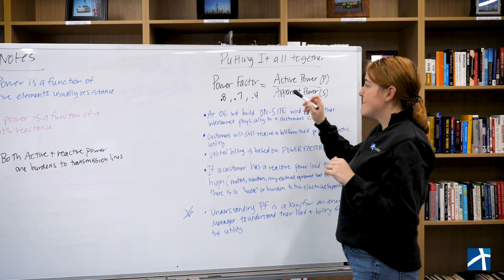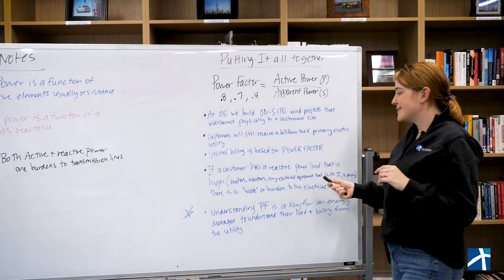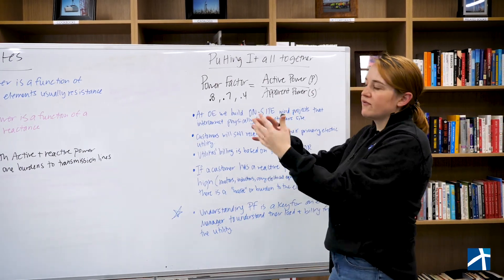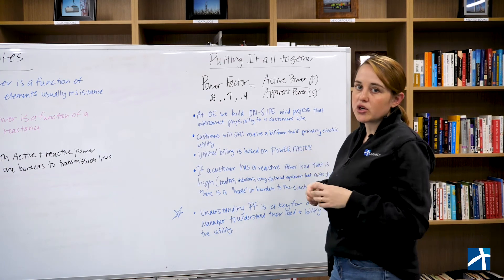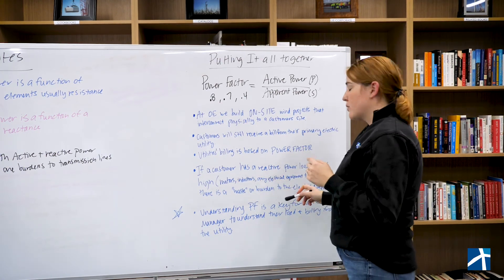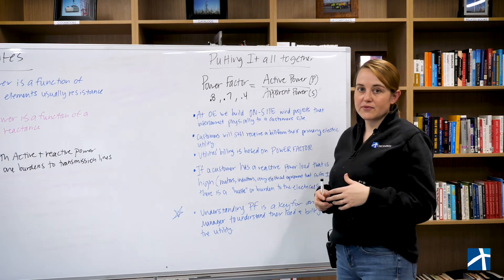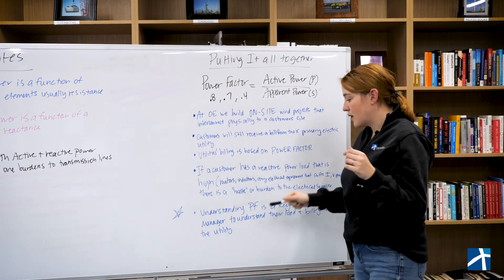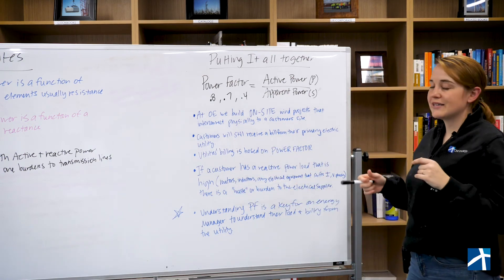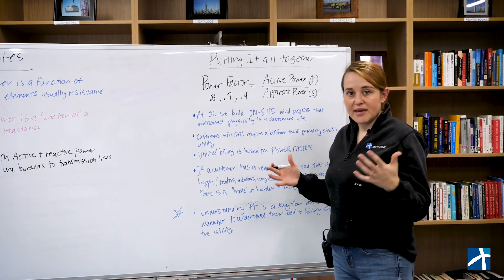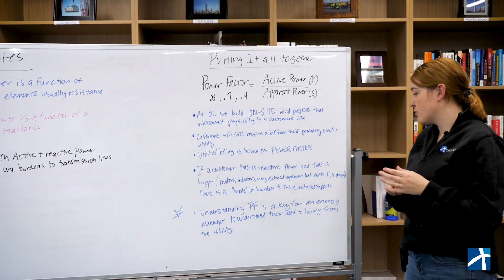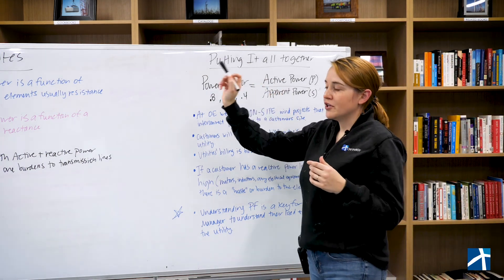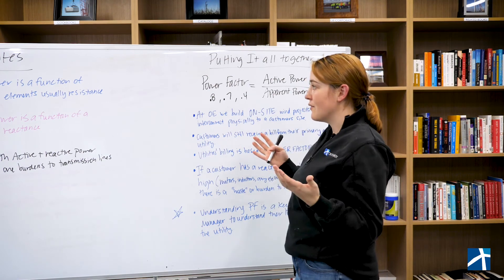So like I mentioned, utilities billing is based on power factor. So if a customer has a reactive power load that is high, motors, inductors, anything that changes that phasing between current and voltage, there's a waste or burden to the electric supplier because of that reactive power. So putting this all together, understanding power factor is a key for an energy manager at any major consumer. So to understand their load and billing from the utility, you need to understand power factor. To understand power factor, you need to understand active and reactive power and how it works.